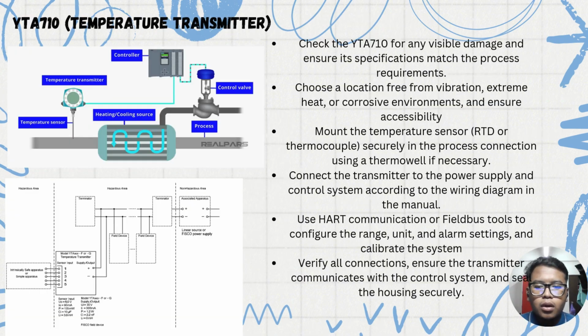This is the installation of the YTA 710 temperature transmitter. This is the step-by-step of how to install this transducer. First, check the YTA 710 for any visible damage and ensure its specification matches the process requirement. Second, choose a location free from vibration, extreme heat or corrosive environment, and ensure accessibility. Third, mount the temperature sensor, RTD or thermocouple, securely in the process connection, using a thermowell if necessary. Fourth, connect the transmitter to the power supply and control system according to the wiring diagram in the manual. Fifth, use HART communication or a fieldbus tool to configure the range, unit and alarm setting, and calibrate the system. Lastly, verify all connections, ensure the transmitter communicates with the control system, and seal the housing securely.